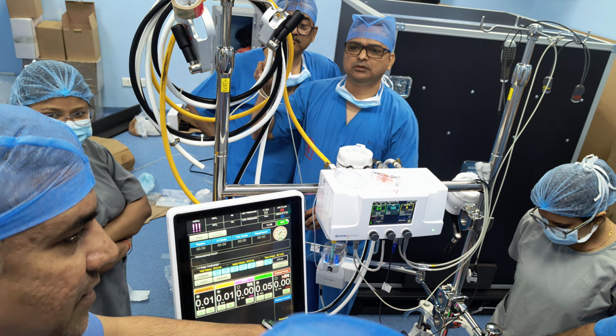It's not institutional. It's a universal color coding. Vent is always yellow. If you open the oxygenator of Medtronic, you get the same yellow cap with the vent line. Green is gas line. So color coding is universal.